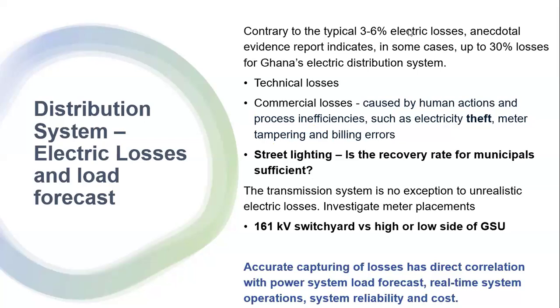Placing your meter matters a lot, because if you've noticed, most generating plants have an aux load, service load, or station load. If you place it such that you are not apportioning the service load or station load to the generator, you will see issues like this. So you need to place your meters at the right locations.